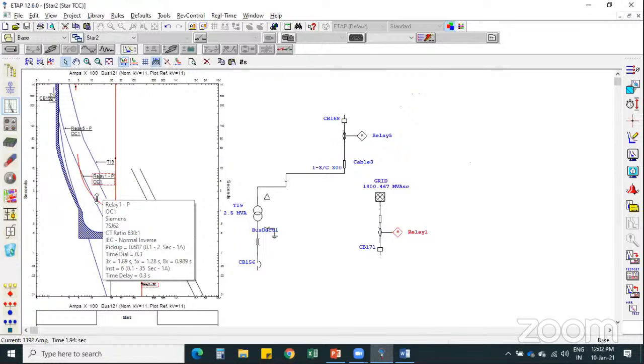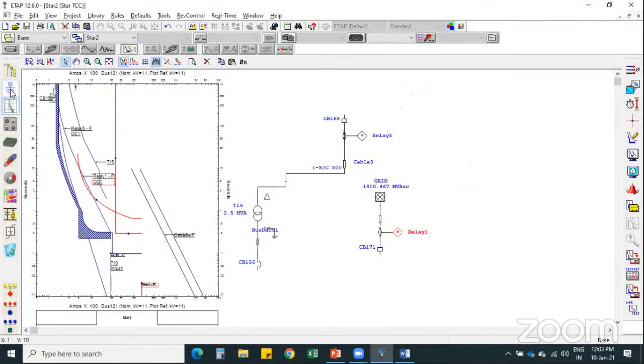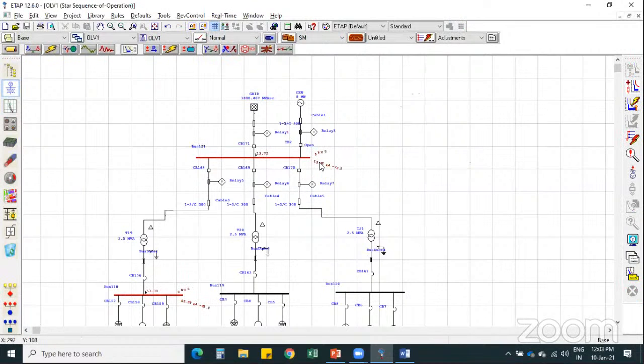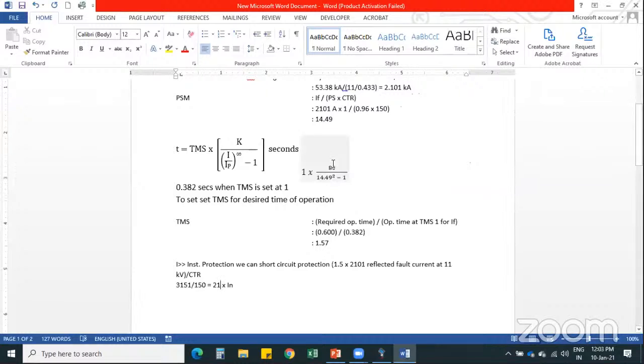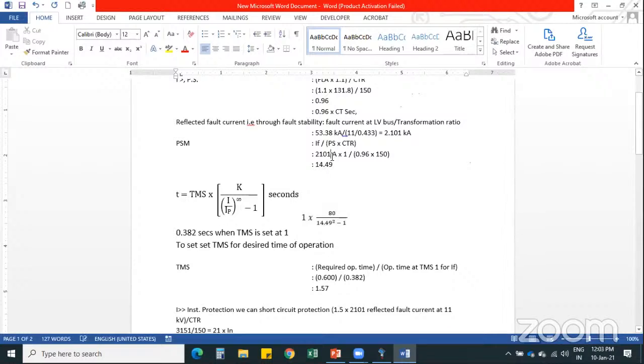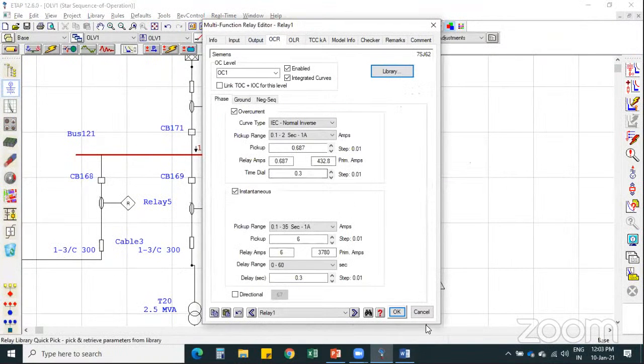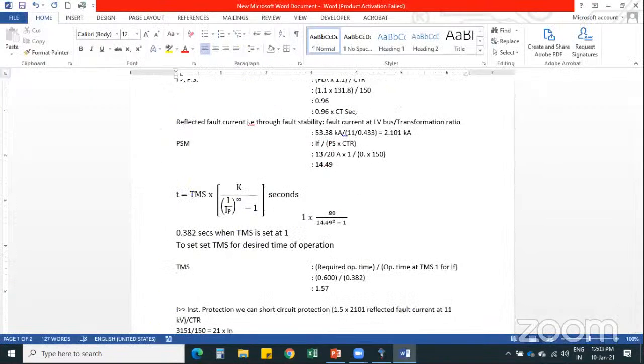Now for this I need to increase the time delay. To change this time delay, first of all we need the fault current value of the particular network, that we can check here. That is 13.72 kiloampere. So we will go for 13.72 kiloampere, we can say 0.678, 687, sorry. CT ratio is 630 ampere. That is 31.69. Now here the PSM is getting much higher, that is 31.69.